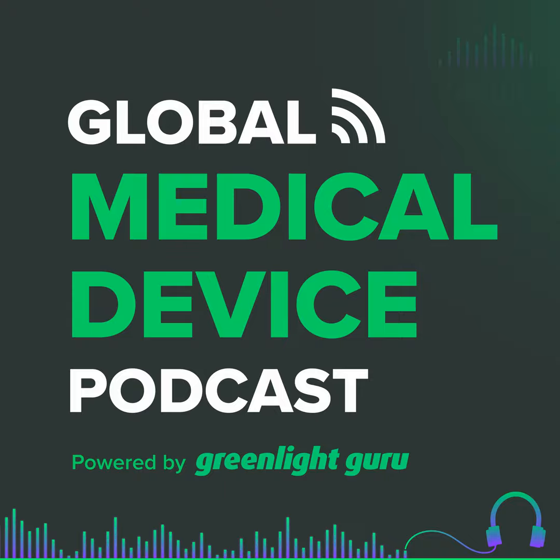Most 510(k) devices, in fact, do not need clinical data. But if you are going to need clinical data, even if it's a non-significant risk device, as we talked about before, I think you're wise to vet that with the FDA in a pre-sub in advance first, even though you're not required to. Some companies take the attitude, well, we don't want to create a problem where none exists. And so they'll say, well, we're not going to tell FDA about that. Well, I say, okay, fine, that's your decision. You don't have to. But here's the risk that you're taking.